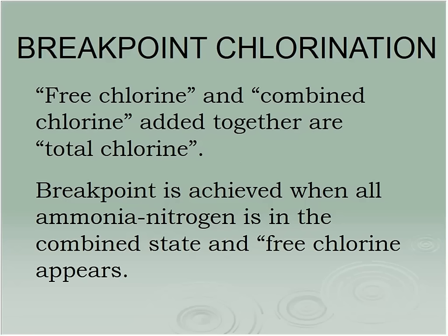Okay, if you have free chlorine, that means I'm reading free chlorine. There's a chlorine ion floating around that water, as opposed to combined chlorine, which is a chloramine, ammonia and chlorine combined. Put them together and you've got total chlorine. A break point is when you've reacted every possible thing in there, and for every little bit of chlorine you put in, you get that amount of free chlorine in your test.